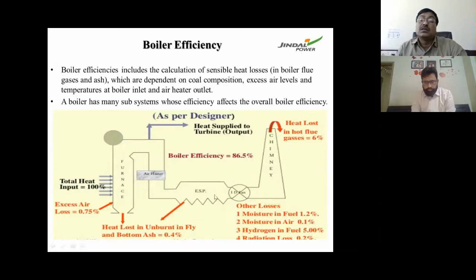There are two methods of boiler efficiency calculation: direct method and indirect method. The direct method is definitely very easy, but it does not give a real picture, because there are limitations of measurement. For boiler efficiency, if we calculate the energy input in the form of coal, the GCV which is measured is not actually accurate. It depends on various factors, because we generally take a sample from a large amount of coal, and with large variations of coal GCV, it does not give the real picture. Similarly, the coal consumption also has some error. So we cannot measure the energy input accurately.